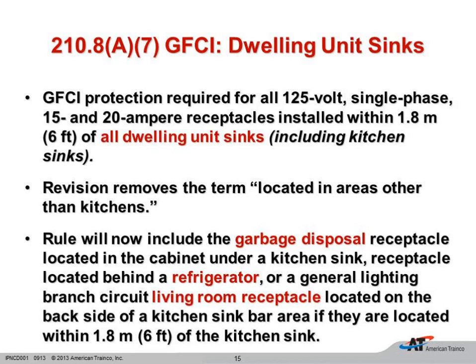And they're going to impact us a little bit. The manufacturers of our appliances are making the motors double insulated, so hopefully it's going to take care of any nuisance tripping. On January 1st, 2008, UL did increase the trip level for GFCIs. They eliminated the 4 and 5 milliamp range, and now the GFCI is going to trip at 6 milliamps or above. So with the new UL standard, and with the manufacturers making the motors double insulated, hopefully we're not going to have much nuisance tripping on these GFCIs, because like you, I grew up at a time when GFCIs did have a lot of nuisance tripping, and with that refrigerator being on the GFI, I get a little concerned, but I'm hoping that the manufacturers have taken care of us on that.